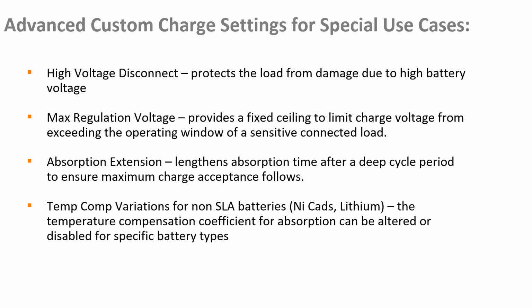High voltage disconnect is one, as I mentioned before, many of our controllers are equipped with load control circuits to run DC loads. So we can monitor the DC load draw from the battery as it is monitored by the controller, and we have this setting built in, high voltage disconnect. It's a voltage threshold that specifies when the load needs to disconnect, because certain loads are more sensitive to higher voltages, especially in telecommunications. So you want to be able to cut them off if the battery voltage is getting high and it's running off the battery. You want to be able to safely disconnect the load so it doesn't get damaged. So that's a useful feature.